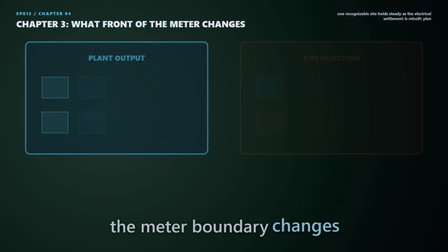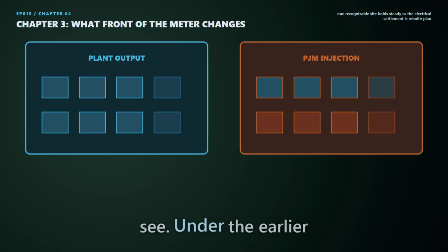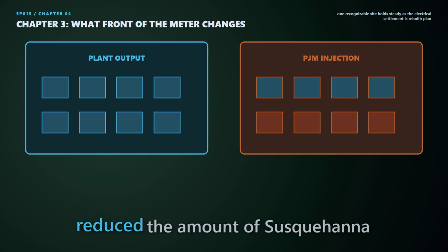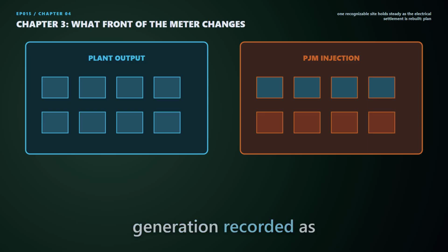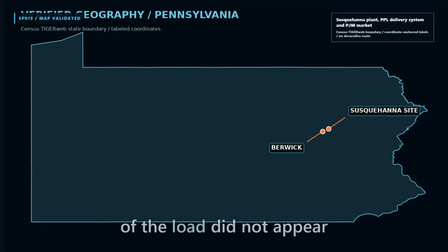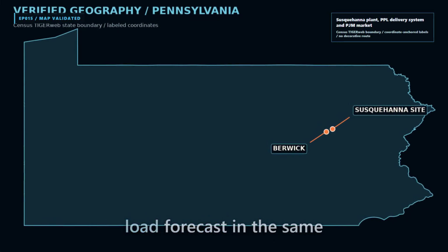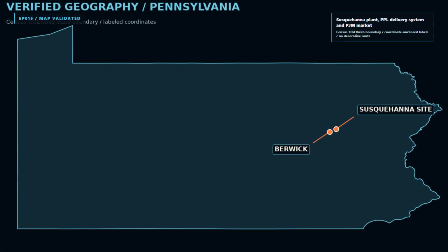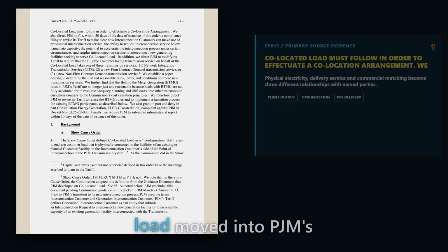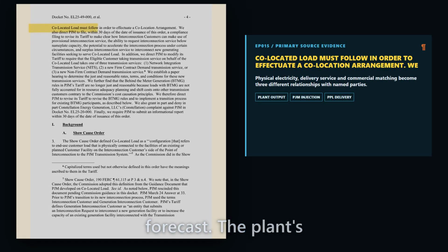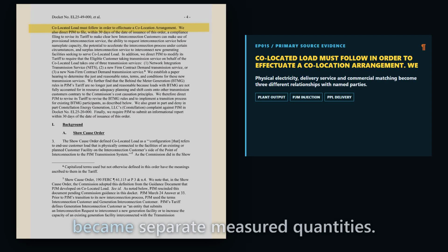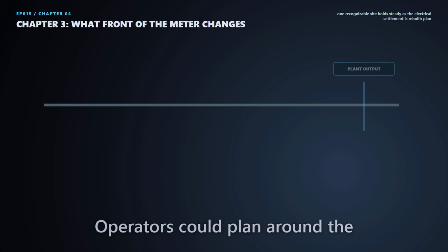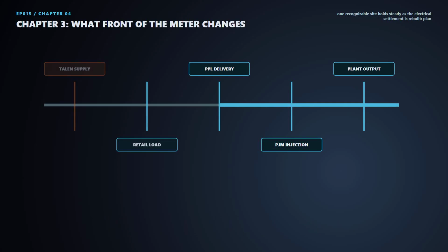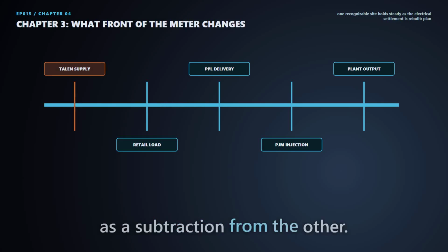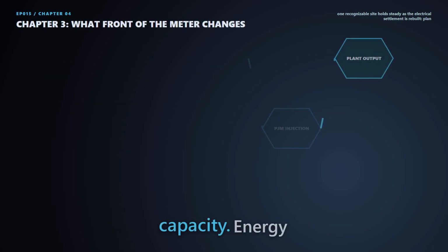Moving the meter boundary changes what the regional system can see. Under the earlier setup, the local campus reduced the amount of Susquehanna generation recorded as entering PJM. Some of the load did not appear in the ordinary regional load forecast in the same way as front-of-the-meter demand. When the arrangement changed, that load moved into PJM's forecast. The plant's output and the campus demand became separate measured quantities. Operators could plan around the full load and the full generator instead of treating part of one as a subtraction from the other. The change also affected capacity.